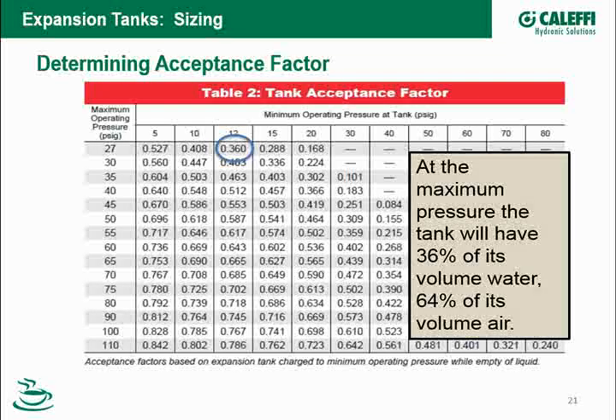In any hydronic system, there's a lot of different relationships going on. The point of no pressure change really is the description of the relationship of the expansion tank to the system pumps or circulators. That truly is the point of no pressure change, and in a few slides we're going to cover that. But from the relationship between expansion of the system water in the expansion tank, the pressure has to go up because I have that air charge that I'm working against, and if I'm going to reduce the volume of the air charge, the pressure has to go up. So I will see the pressure change, but it's really the relationship of change in temperature, and it's independent of pump operation.